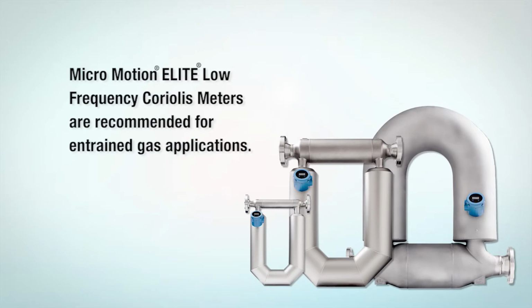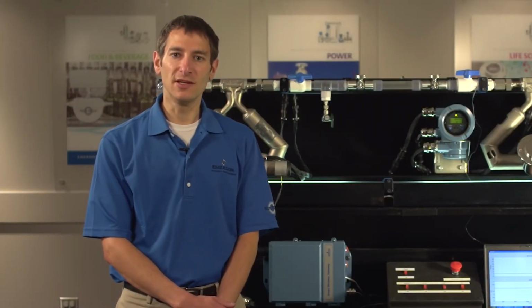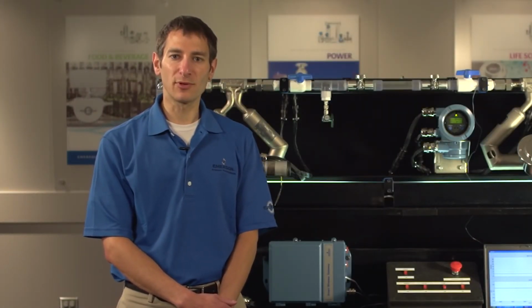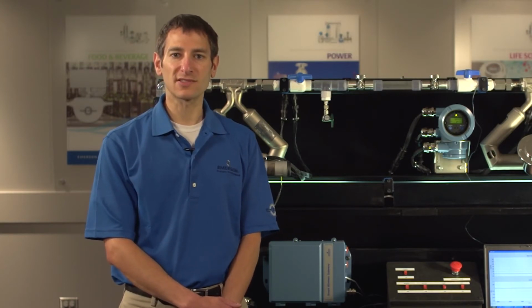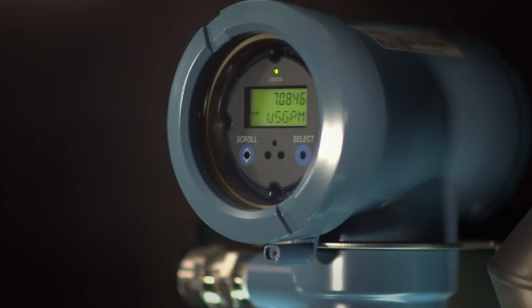While Micromotion manufactures meters with a range of frequencies from low to high, our low-frequency Elite meters are recommended for applications involving entrained gas, as they are usable over a much larger range of gas volume fractions than a high-frequency meter. Aside from having a low vibration frequency, Micromotion meters improve immunity to entrained gas by employing a state-of-the-art transmitter with the latest in digital signal processing algorithms.